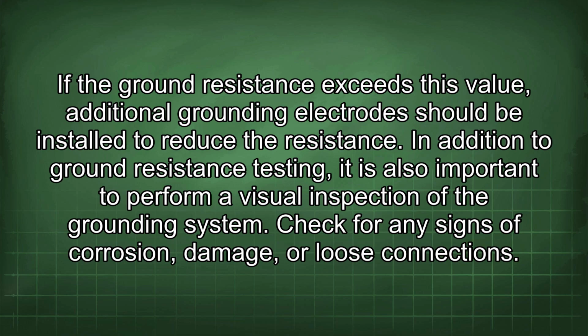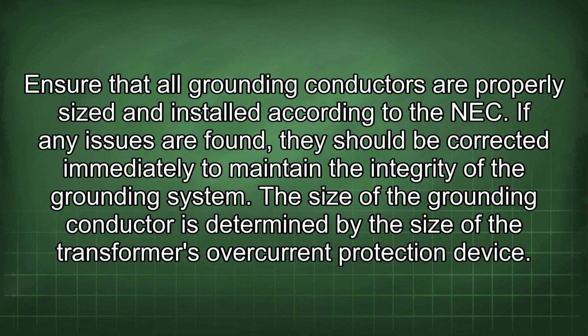In addition to ground resistance testing, it is also important to perform a visual inspection of the grounding system. Check for any signs of corrosion, damage, or loose connections. Ensure that all grounding conductors are properly sized and installed according to the NEC. If any issues are found, they should be corrected immediately to maintain the integrity of the grounding system.